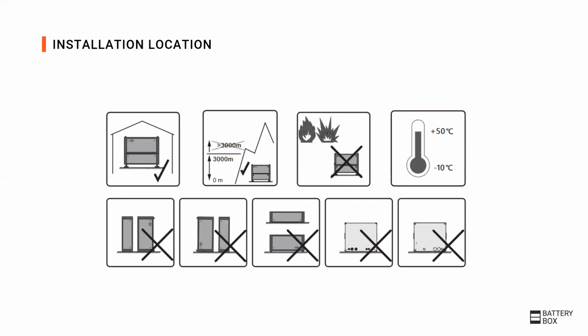Here you see the requirements for the installation location. The temperature range is again from -10 to +50 degrees, and the battery power will be limited below 5 degrees. The battery should not be placed close to easily inflammable material. The battery has a protection rating of IP20 and should be placed inside to protect the battery against weather conditions. The battery should not be placed on the side, but always in the correct direction.